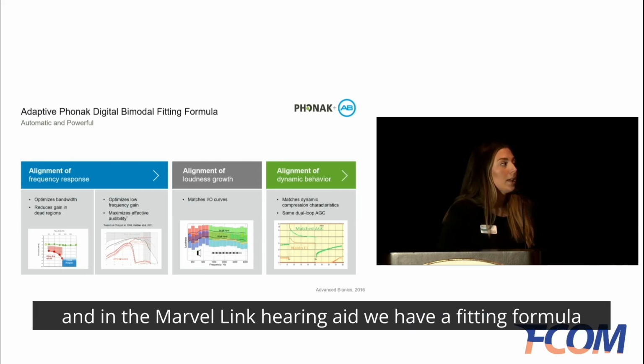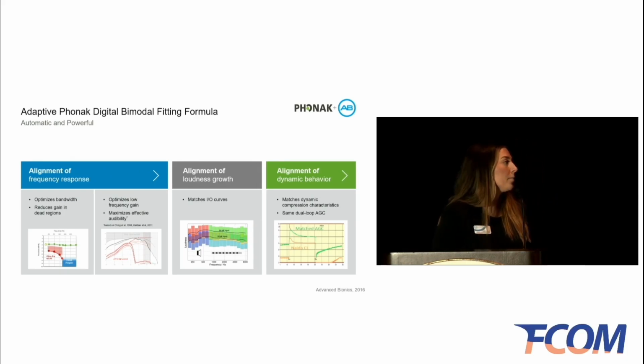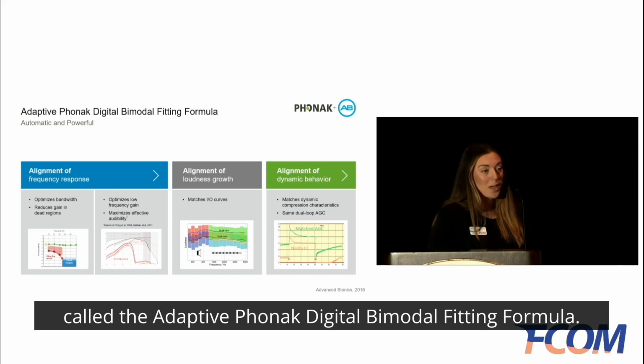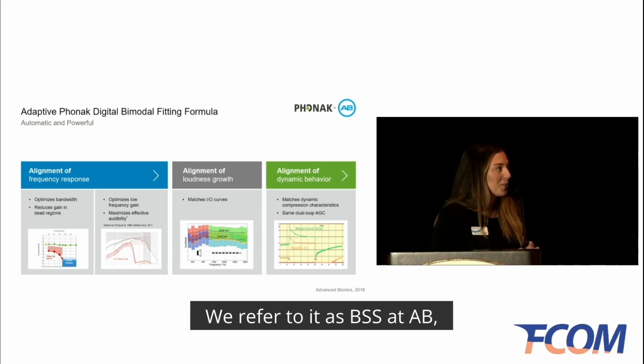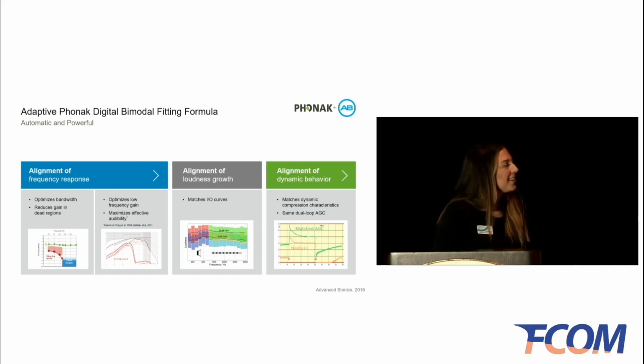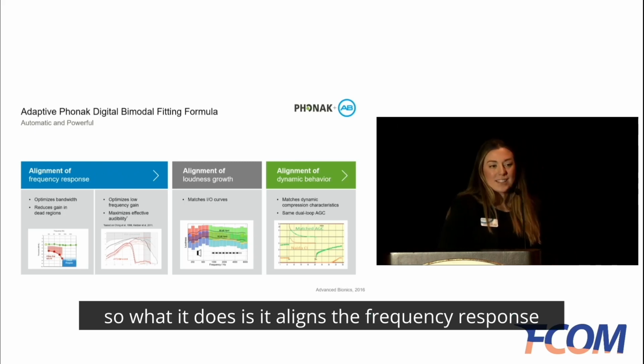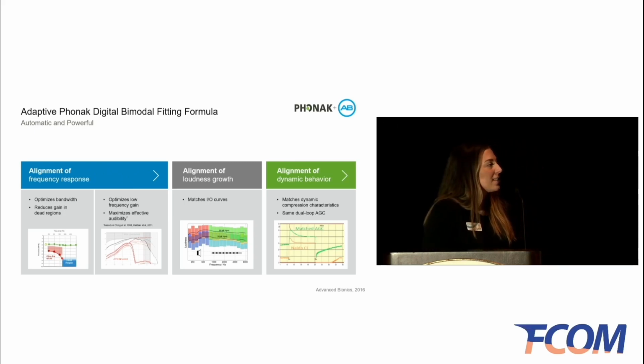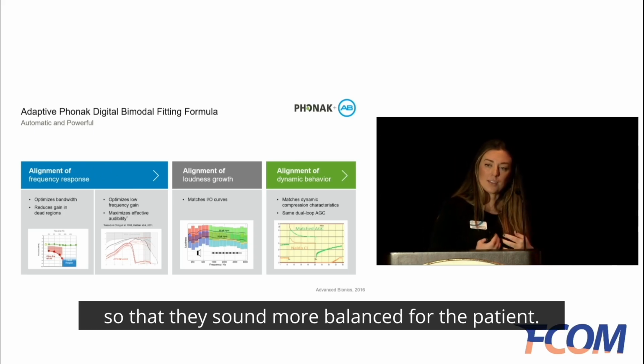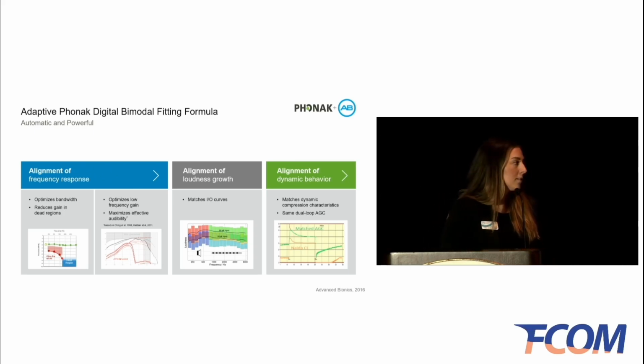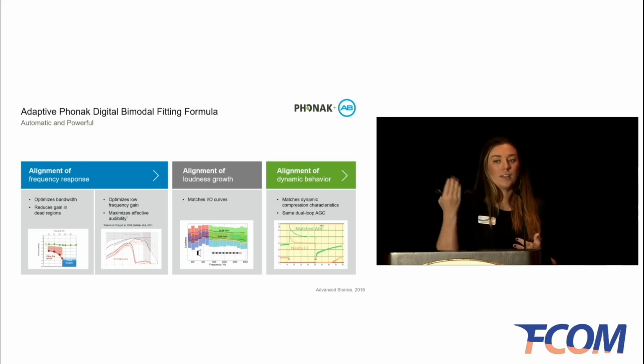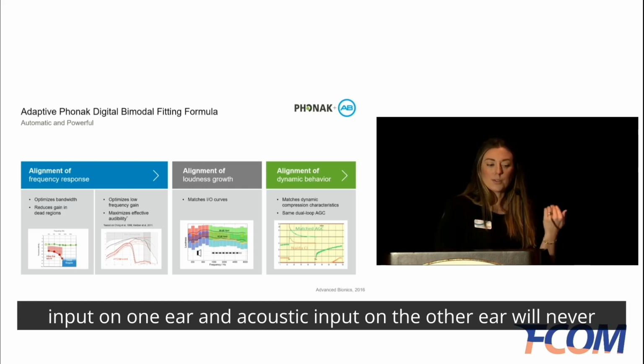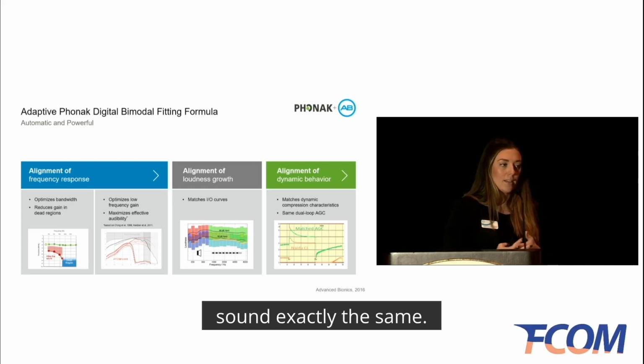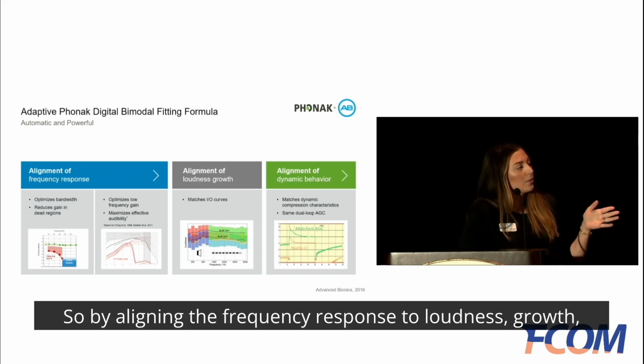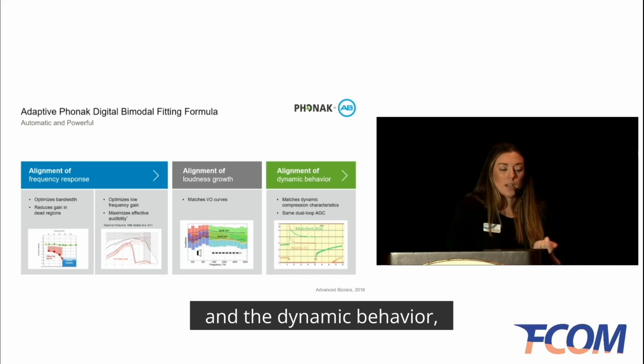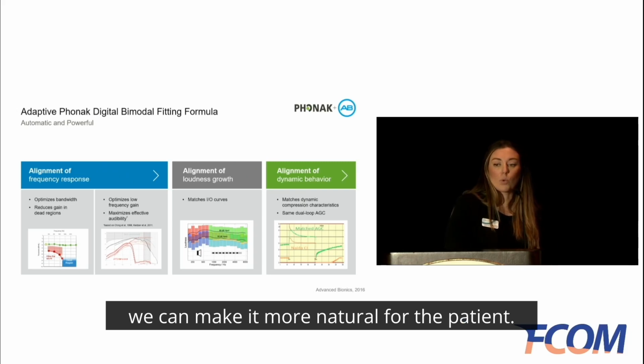And in the Marvel Link hearing aid, we have a fitting formula called the Adaptive Phonak Digital Bimodal Fitting Formula. We refer to it as BFF at AB. So what it does is it aligns the frequency response of both the hearing aid and the CI so that they sound more balanced for the patient. Because if you think about it, electric input on one ear and acoustic input on the other ear will never sound exactly the same. So by aligning the frequency response, the loudness growth, and the dynamic behavior, we can make it more natural for the patient.